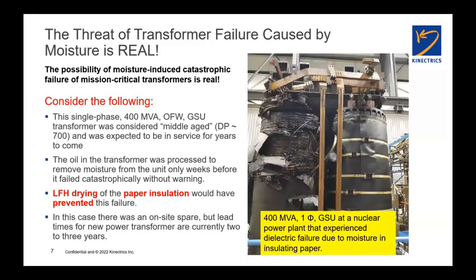You know, the threat of transformer failure being caused by moisture is very real. Picture that you see there is of a large generator step-up transformer at a nuclear plant. This was a forensic analysis, failure analysis that Kinectrics was involved in the aftermath of this unit exploding, which is basically what happened. You can see it's this particular unit, it's a single phase core type transformer, about 400 MVA.